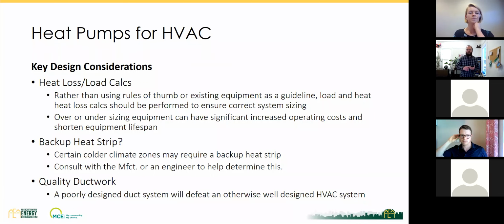So some of the key considerations for utilizing heat pumps for your HVAC is doing heat loss or load calcs rather than using rules of thumb or existing equipment as sizing guidelines. Load and heat loss calcs should be performed to ensure correct system sizing. Over or undersizing equipment can have really significant increased operating costs and also significantly shorten equipment lifespan. So we want to make sure that the equipment is sized correctly for the building and not just a direct replacement for whatever was there before.